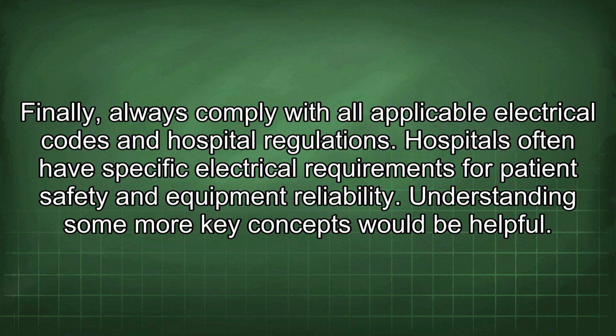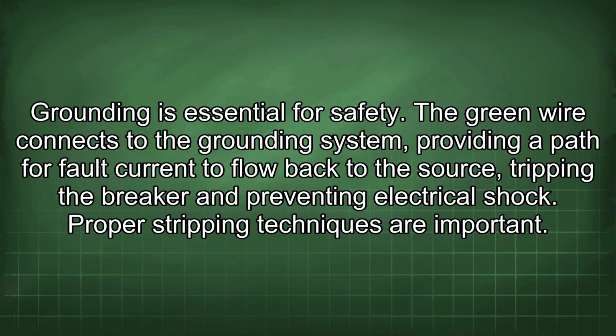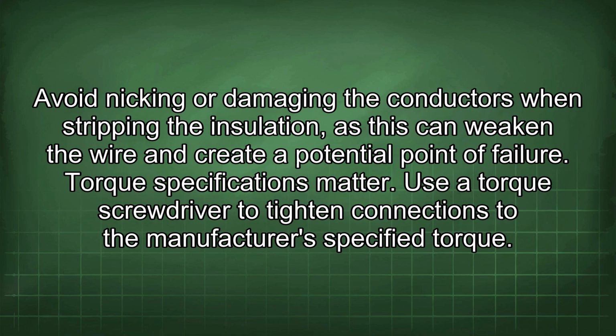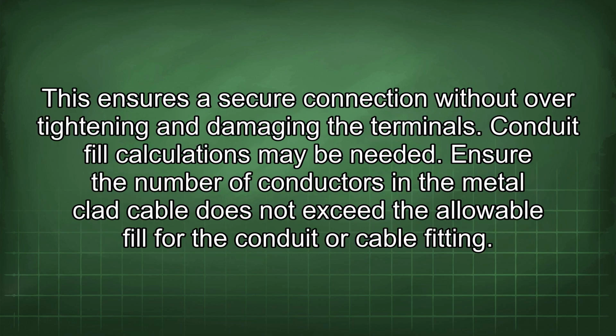Understanding some more key concepts would be helpful. Grounding is essential for safety. The green wire connects to the grounding system, providing a path for fault current to flow back to the source, tripping the breaker and preventing electrical shock. Proper stripping techniques are important. Avoid nicking or damaging the conductors when stripping the insulation, as this can weaken the wire and create a potential point of failure. Torque specifications matter. Use a torque screwdriver to tighten connections to the manufacturer's specified torque. This ensures a secure connection without over-tightening and damaging the terminals.